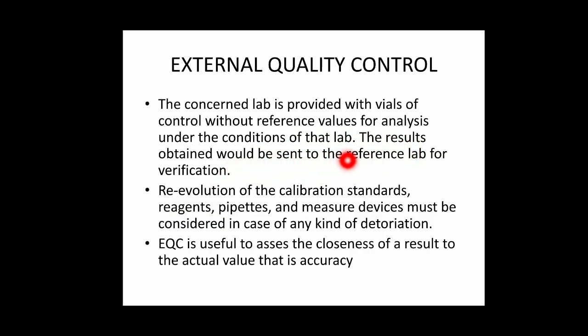The lyophilized form we have to reconstitute, which means we have to dissolve it with a certain amount of distilled water. The procedure will be given, we have to follow that, and we have to run the parameters. Once we get the report of this quality control, we will not know how much the value should be. So we have to reconstitute it properly, then run the tests we are interested in. Whatever report we are getting, we have to send it to the reference lab for verification.